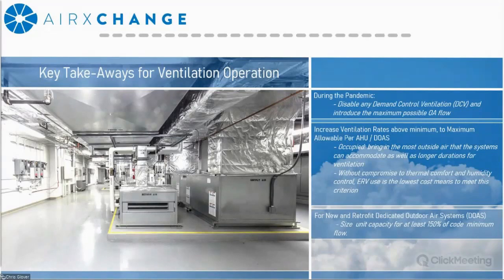Increase the ventilation rates above the minimum rates to the maximum allowable per the device without compromising thermal comfort or humidity control. And if the building is considering replacing or designing a new ventilation unit, size that unit for 150% of the code mandated minimum flow for periods of crisis. As a word of caution, when changing the operating parameters of an HVAC system, there may be both intended and unintended consequences. So you want to make sure that you have a good understanding of the system effect before implementing any of these changes.